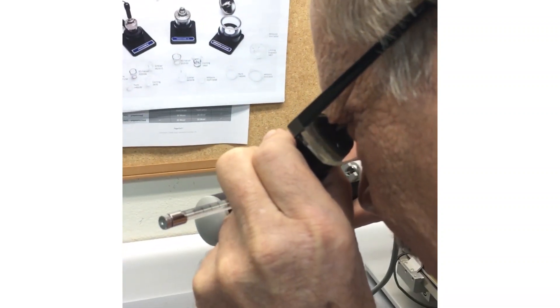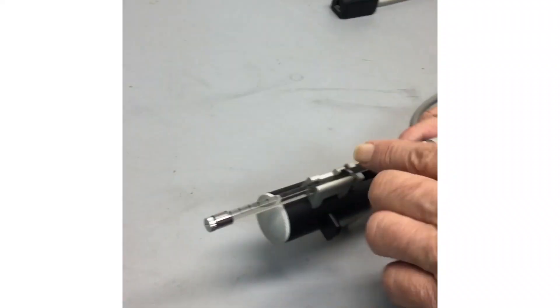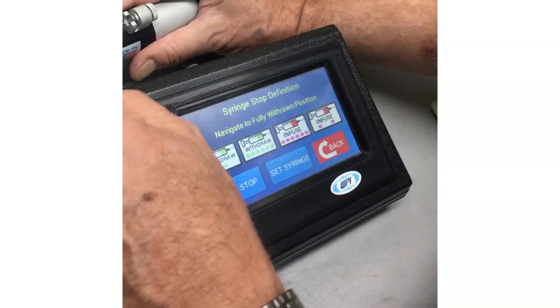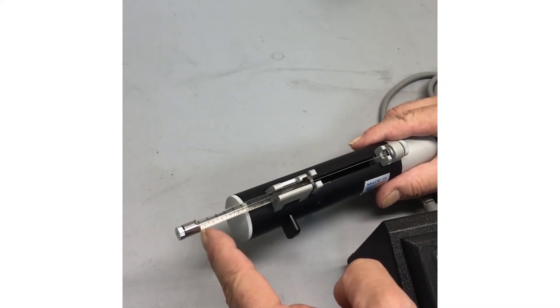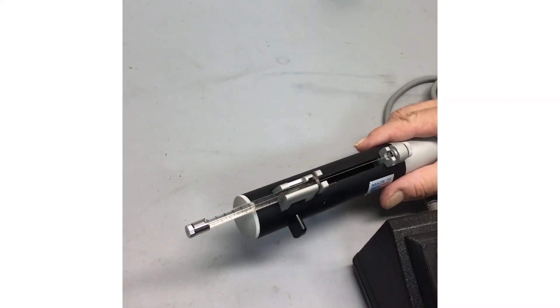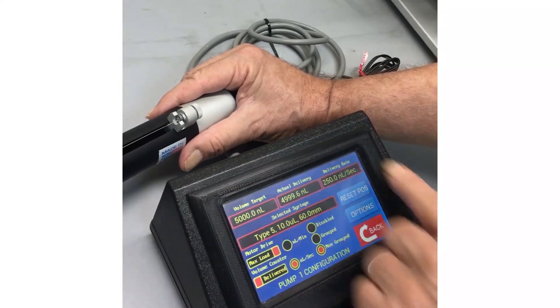In this particular case, it's right there — exactly at that mark, actually a little bit slightly forward of that. Normally it's one millimeter above. So what we would do is push the infuse button until it lines up with that full mark on the syringe, and then at that point we do set syringe. Now the machine knows where the top of the syringe is, so it knows it can travel 60 millimeters forward and not try to drive below the zero mark. This now has a memory programmed into the machine — it knows exactly where the syringe is at every moment in time.